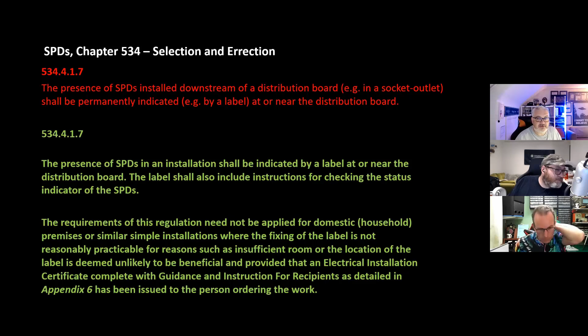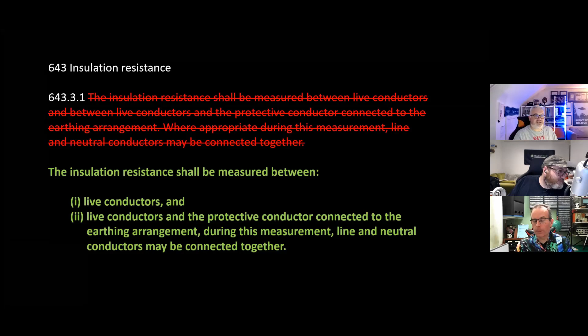Right, so part 6, inspection and testing. A couple of reg changes, just very minor formatting. 643.3.1, the insulation resistance shall be measured between live conductors and between live conductors and protective conductor. It was poorly worded. It's now formatted like that. The insulation resistance shall be measured between live conductors and protective conductor connected to the earthing arrangement. During this measurement, line and neutral conductors may be connected together. So they've just formatted it. No real change there whatsoever, just a formatting issue.